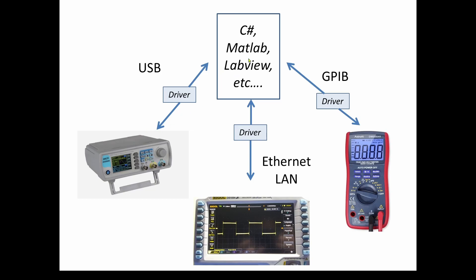So why would you need that? In a future series coming up very soon, we're going to show how to do this using software on our computer so that we can program these devices to perform what's called an SFRA, or sweep frequency response analysis, like we talked about in a previous series. Basically, allowing you to change the frequency coming out of the signal generator that we feed into a transformer, and the output of that circuit is measured on our oscilloscope, so we can do an SFRA analysis of the transformer to determine whether it's good or bad. Ultimately, it will take the frequency and voltage values and plot voltage versus frequency.